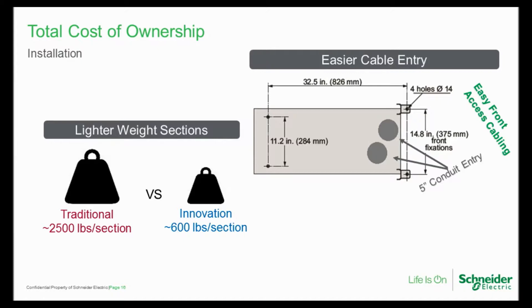Traditional switchgear is considerably larger than the new generation of medium voltage products, and the benefits are considerable. First, this design aspect, and then as we move forward, the fact that it's small means it's also very light — and lighter switchgear is easier to handle. A significant installation cost is in moving the switchgear over already-positioned conduits, which usually takes cranes, forklifts, sometimes not available due to space constraints. In the case of Premset, for example, we're talking about 600 pounds compared to the equivalent switchgear at maybe 2,500 pounds.